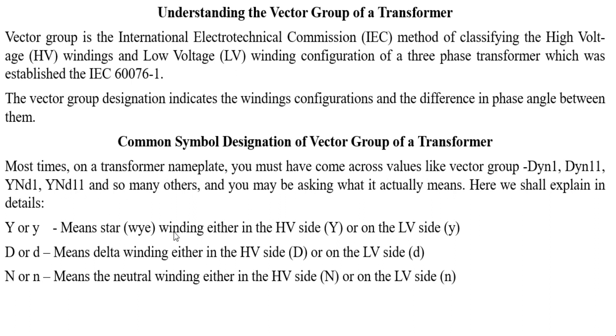All these are the different configurations on the transformer name plate. Capital Y or small letter Y means the winding is connected in star — capital Y signifies the high voltage winding, small letter Y signifies the low voltage winding. Capital D or small letter D means delta connection — capital D means the high voltage winding is delta connected, small letter D means the low voltage winding is delta connected. Capital N or small letter N indicates the neutral of the high voltage or low voltage winding respectively.